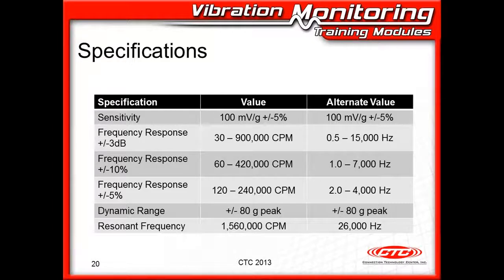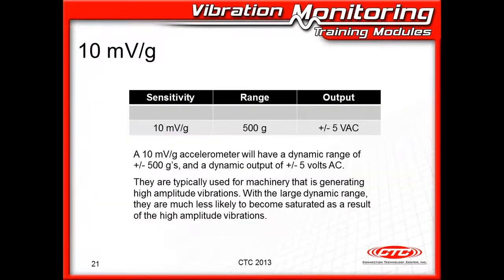Each sensor comes with specifications. Those will be found on the data sheet for that sensor. And you'll see things like sensitivity, 100 millivolts per G plus or minus 5%. The frequency response at 3 dB and 10%. And maybe if this is a premium sensor like we're showing here at 5%, we'll see the dynamic range. How much vibration can this sensor have before it saturates? And what is the resonant frequency? In this case, it resonates at 26,000 hertz.